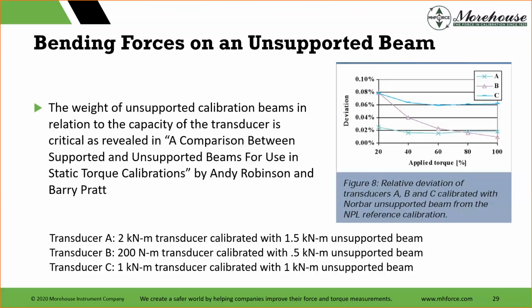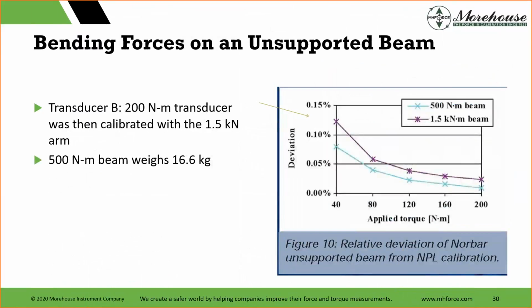200 newton meter transducer calibrated, and you look at these errors, these are all the applied torque. Look how high those errors are, and that's just from the weight of the beam. And we're going to dissect that a little more. So transducer B, 200 newton meter transducer was calibrated with a 1.5 kilonewton arm. 500 newton meter beam weighs about 16.6 kilograms. Look at these errors. So 500 newton meter beam calibrating a 200 newton meter transducer, and you can see as you approach capacity, they get better. But at those lower points, say even at your 20% point, the errors are really, really large. And this is what people don't realize. That's all bending.